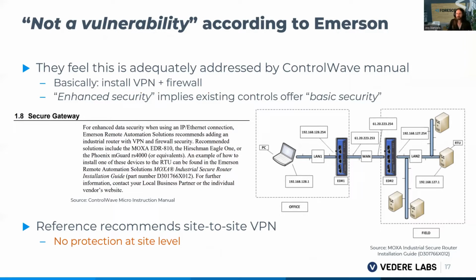On top of that, the proposed reference design, which you can see on the right of the slide, doesn't offer any protection against this issue at the site level itself. It proposes you have the remote location where the engineering workstation is, and the satellite site where the PLC lives, with a site-to-site VPN connection between them. But if you have any sort of compromise at the site location where the ControlWave is, and there isn't adequate segmentation there—which you might not do because you're led to believe this authentication is good enough, especially with this site-to-site VPN—then you have residual risk there, which is unaddressed. So not considering this a vulnerability, and not mentioning what quality of security you can expect of secure mode 2, might lead to accepting more risk than you actually have an appetite for. And that's unfortunate in my opinion.